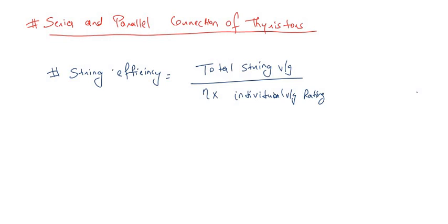It is a measure of utilization of SCR rating. Similarly it can be total string current, and here individual current rating can also be used if we are connecting them in parallel. So string efficiency is a measure of how much we are utilizing the thyristor.